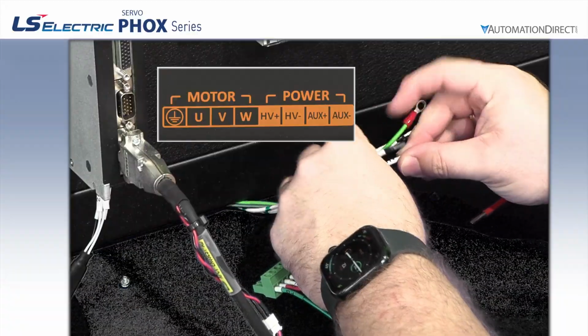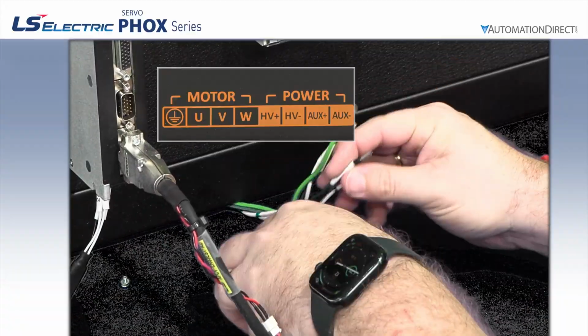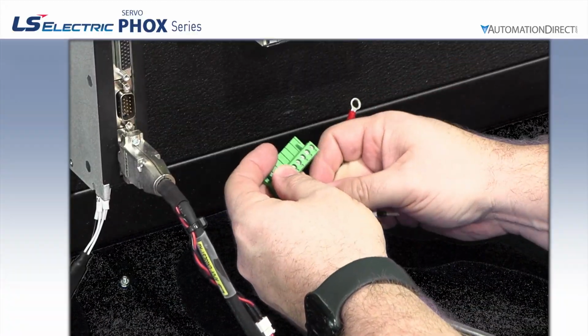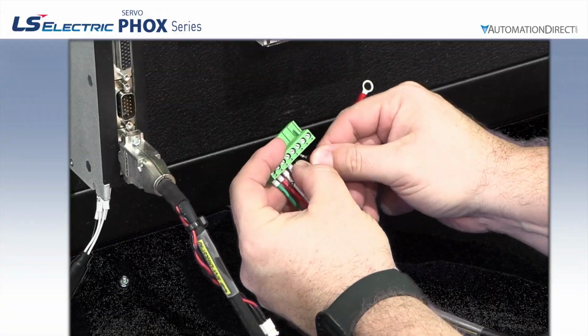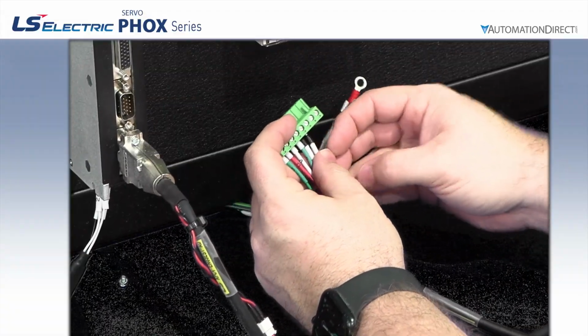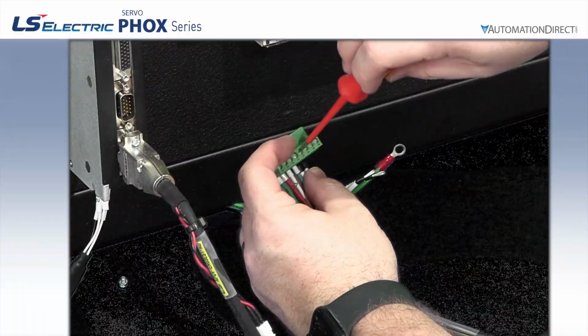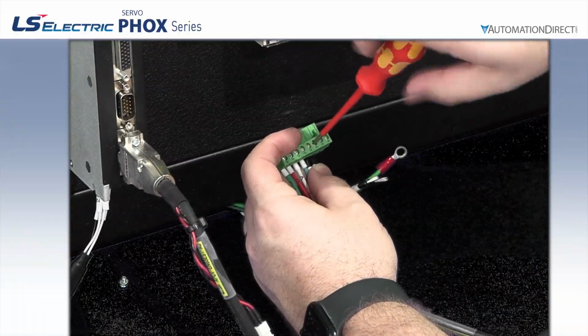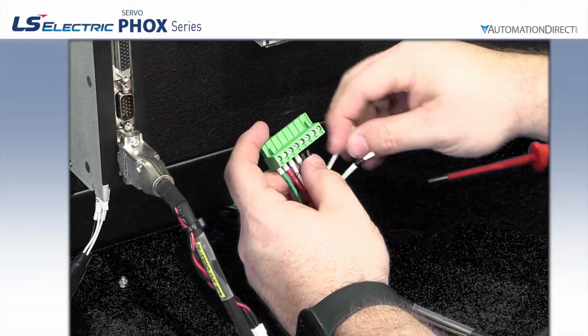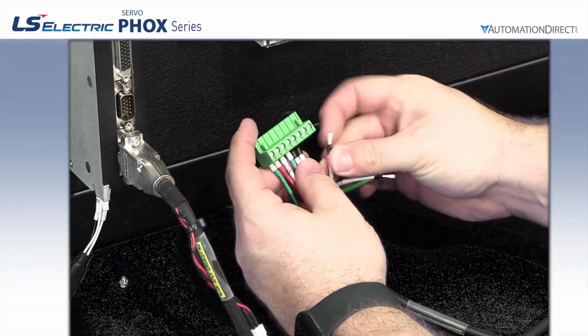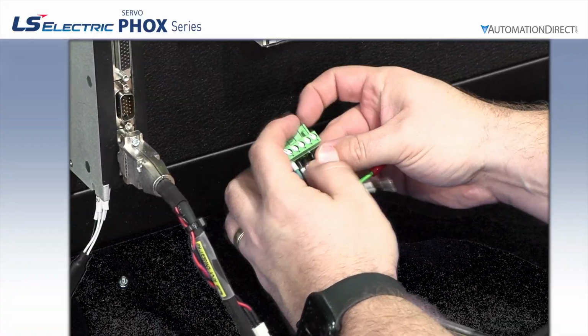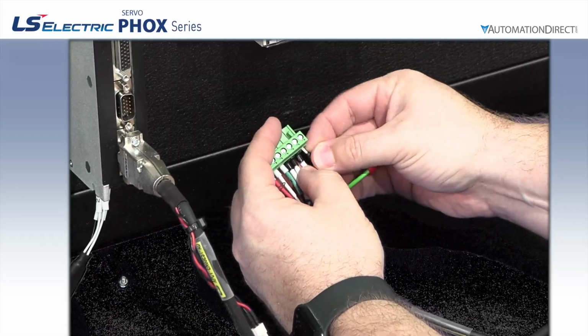Verify the wire labels match the printing on the side of the drive. Next, connect the 24-volt DC drive main power wires from the power supply to the 5th and 6th positions for HV plus and HV minus. If you are using auxiliary power like we are here, connect the 24-volt DC control power wires from the control supply to the last 2 positions for aux plus and aux minus.